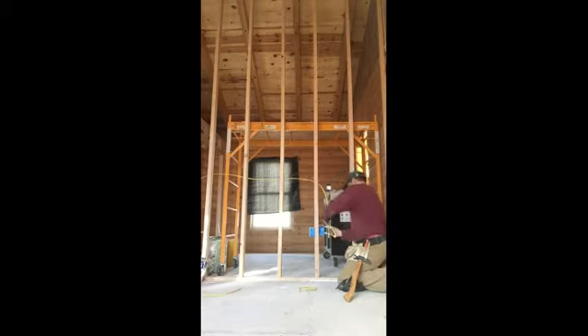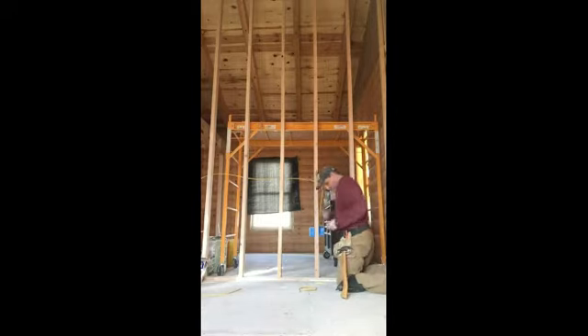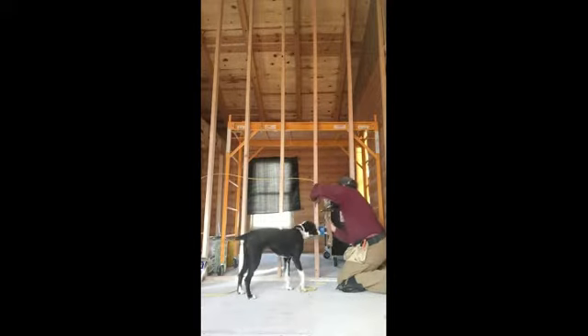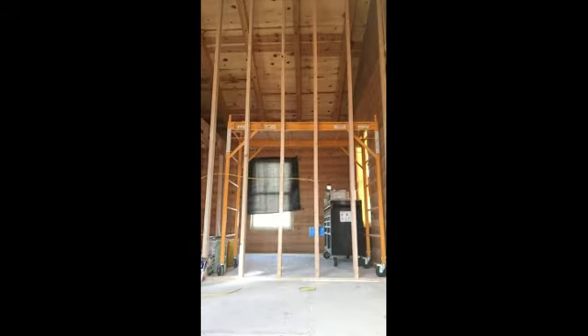The next step is nailing all the circular boxes for your light fixtures. This would include any lights that are going to be installed, such as recessed lighting, chandeliers, and ceiling fans. If you have anything else special in the room, I say like a jacuzzi, sauna, which will need ample power, then you'll also need to nail in an outlet box where the power is going to be harnessed from the wall outlet. So plan ahead and really think this through on your wiring diagram.